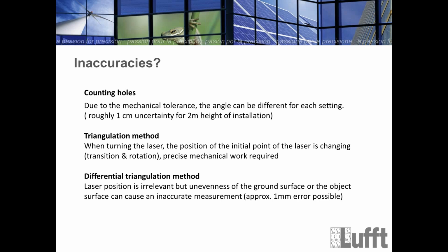This is a little bit undefined. The reason is you also have some mechanical play. If you do this installation here, you see that there is some play. If you release it and mount it again, you must be careful to do it in the original position, because you compare two results, and so the total error might be in the same range as the counting hole method.